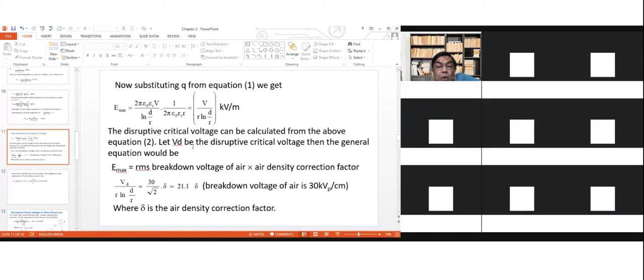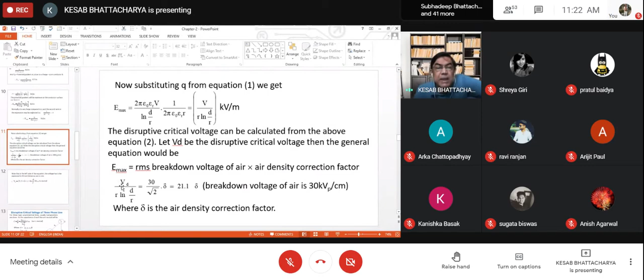Now, in the next slide, note that on the left side of the equation, the voltage has to be expressed in kV and the distance in centimeters. 30 by root 2 is 21.1, into delta. So Vd by R ln d by R is equal to 21.1 delta. Therefore, Vd, the disruptive critical voltage, is equal to 21.1 into delta into R ln d by R kV RMS to neutral. We consider the neutral plane, so this is not the line voltage. This is the phase voltage, the voltage from line to neutral. So this is the RMS value of the phase voltage, 21.1 into R into delta into ln d by R.